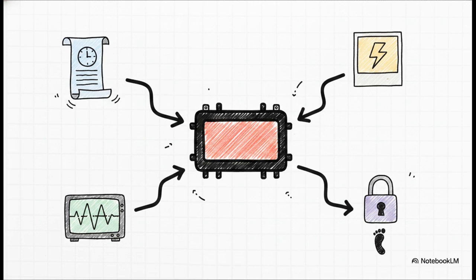First, you have your sequence of events, which logs a running diary with millisecond timestamps. Then you have fault records, capturing snapshots of the latest faults. Next is the disturbance recorder, which captures actual waveforms in ComTrade format for cross-vendor analysis. And finally, the audit trail keeps track of all security-related events and logins.